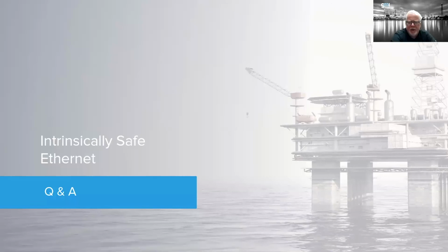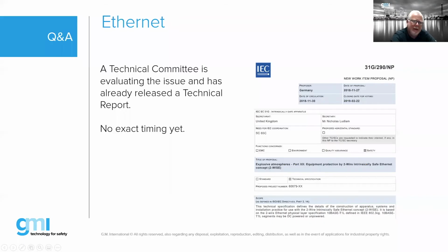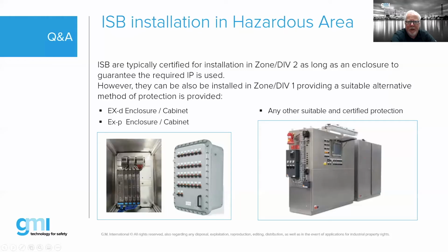Now, one thing that people sometimes fail to remember is a lot of barriers, including GMI, can actually be installed into a Zone 2, Div 2 application. So they're actually certified to be installed in a hazardous location. They cannot be installed in a Div 1, Zone 0, or Zone 1 application unless you put them, say, in a flame-proof or explosion-proof box. So that's one way you can address it, possibly by shortening the cable. Let me show you that. That is a question we had prepared an answer for, and that is exactly what it is. So you can install a barrier into a hazardous location, providing you have a separate method of protection, like here we show an explosion-proof box or an EXP box. Right.